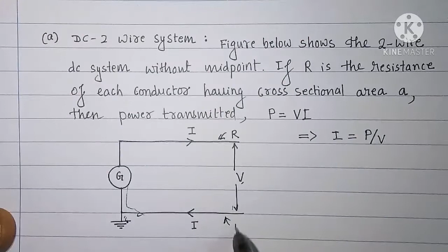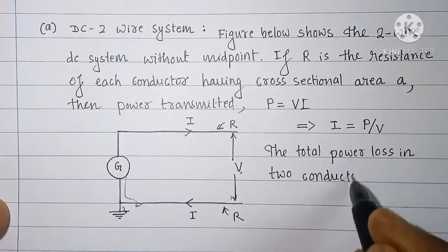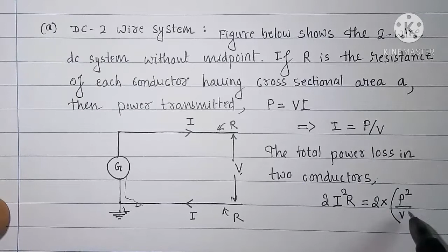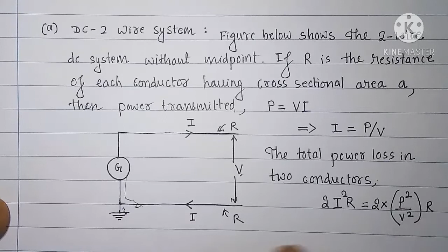Since resistance of each conductor here is R ohms, the total power loss in two conductors is 2 times I square R. Loss in one conductor is I square R, but there are two conductors, therefore it will be 2 times I square R. That is equal to 2 into I is P by V. Therefore we can write I square as P square by V square into R.